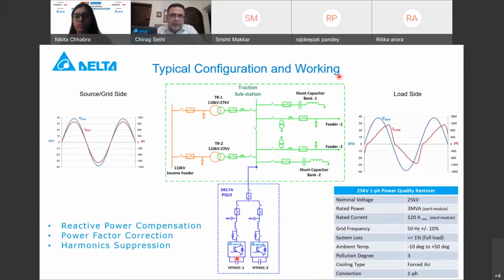This is an SLD of a traction substation, where the left side is the incoming, the grid side from where we tap energy, we step it down, and then we feed the loads towards the right side. Due to the non-linear nature of loads, there are always some harmonics which are transmitted to the source side. What we have implemented here is, at the 27 kV feeder bus, we have provided our power quality compensation equipment, whereby at the source side, at the point of common coupling where the metering happens, we get a pure sine wave, if I may say.